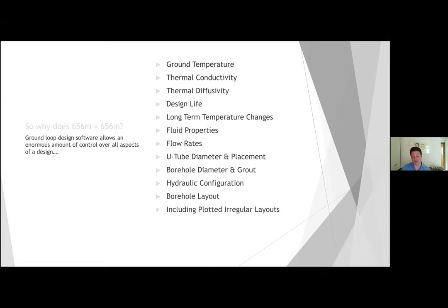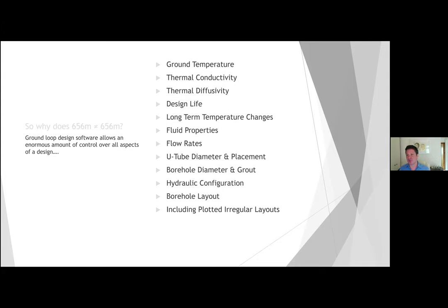Today I'm going to use borehole layout — specifically plotted irregular layouts — as an example of how a system specified at 656 metres ended up with something different. The key point is that all of these parameters make a difference. None of them are insignificant in ground loop design, and we only really have control of two of them in the MCS tables.